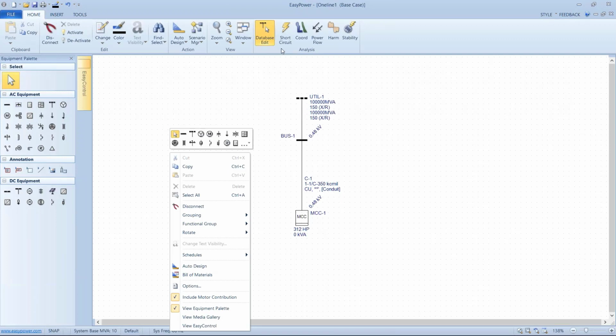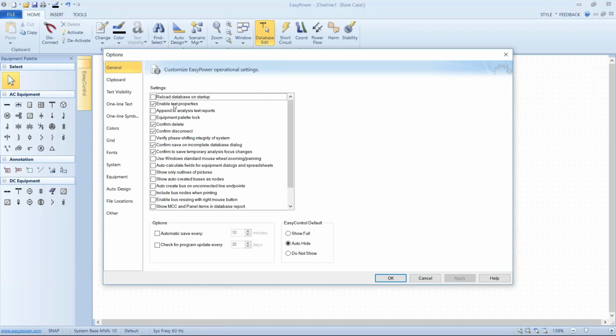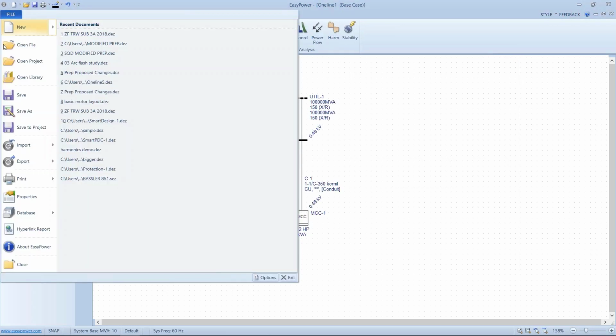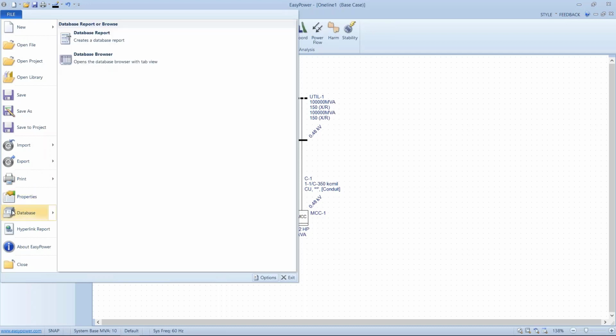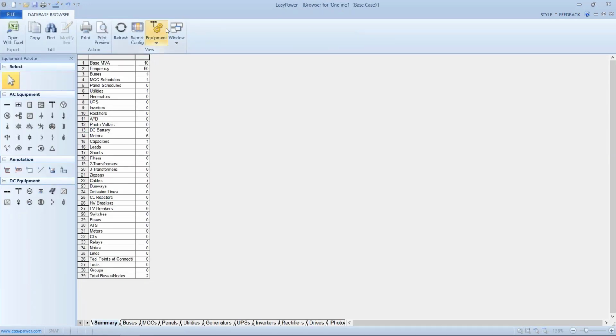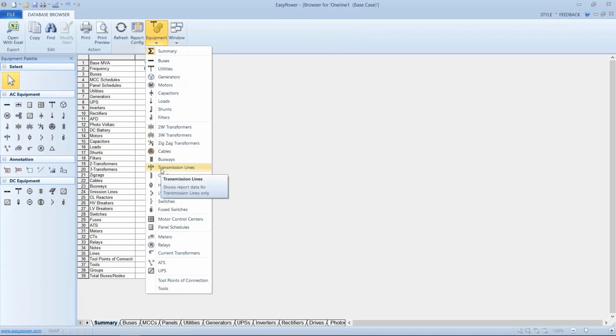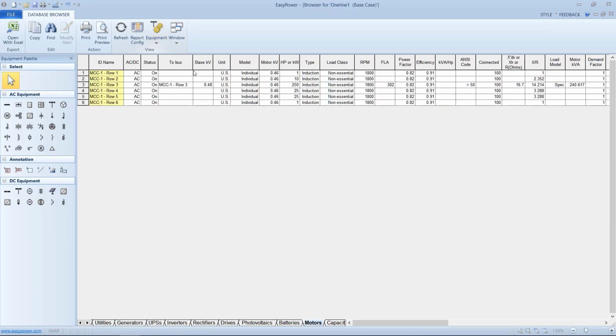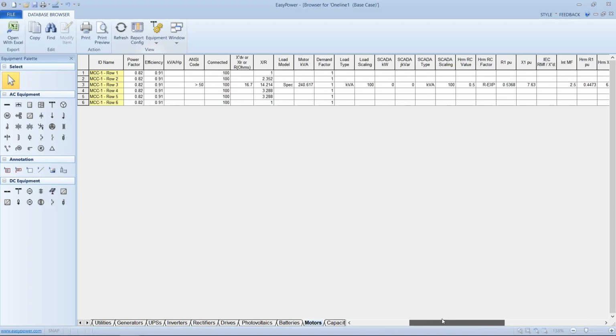Well, if I come back out here, I'm in database edit. I right click in an open area and I look at options. One of the general options is include or show motor control center and panel items in database report. Now, if I apply this, I go back to my database browser and I look at motors. Now all my loads are in there and I can see where I have things completed and not completed as far as the data that's been entered.